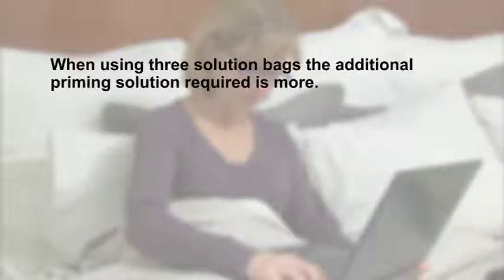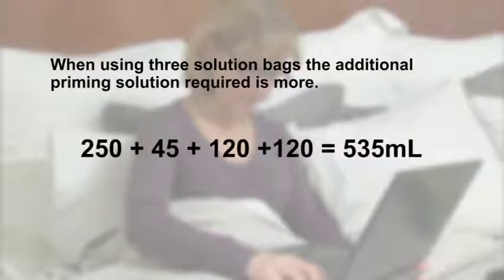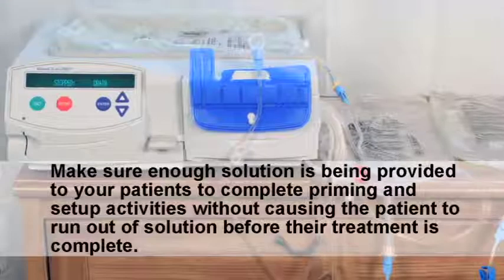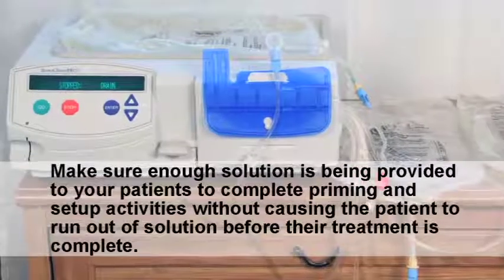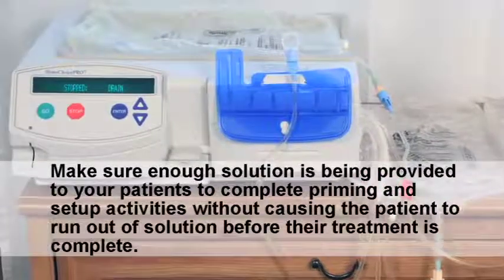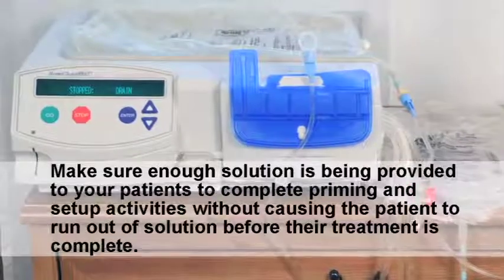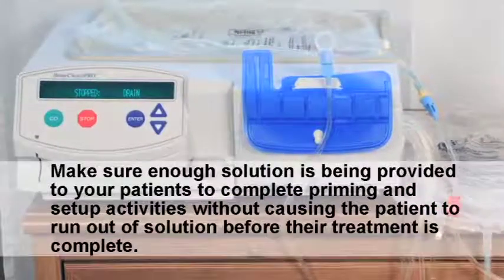When using 3 solution bags, the additional priming solution required is more. In this case, 250 milliliters to prime the heater bag and complete the integrity test, plus 45 milliliters to prime the patient line, plus 120 milliliters to prime each of the supply lines. This would equal 535 milliliters of solution. Make sure enough solution is being provided to your patients to complete the priming and setup activities without causing the patient to run out of solution before their treatment is complete.